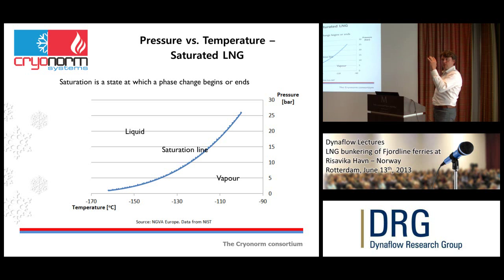By topping up, bringing the LNG on top of the tank and spraying the cold LNG into the hot LNG sitting on top, you bring down the pressure. This ensures the safety relief valve setting is not reached while filling the tank, either on top or bottom. That's how the system operates.